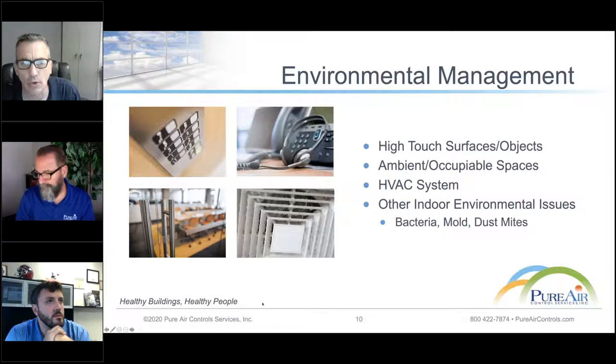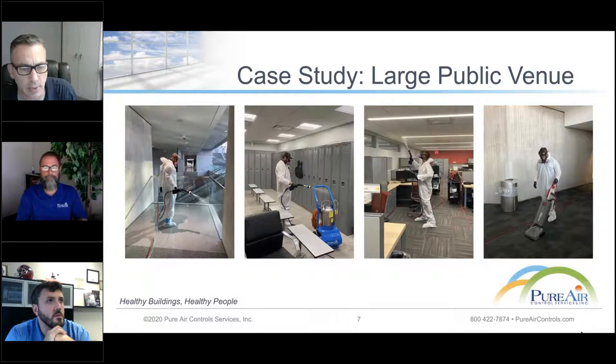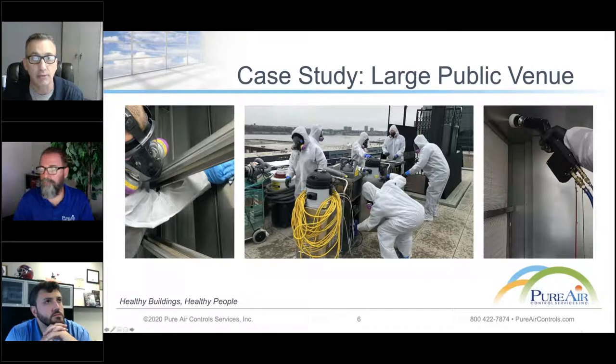The basic process was: they went up to the roof every day, dressed in their PPE. We opened up the units and did a HEPA vacuum of each unit. Once all the units were HEPA vacuumed, we used an approved disinfectant and electrostatic spray guns, disinfecting the whole unit — through the walls, the coil, the blower wheels, every part from top to bottom. Once done with one unit, we moved on to the next. We also did testing on these units to clear them, taking surface swab samples.